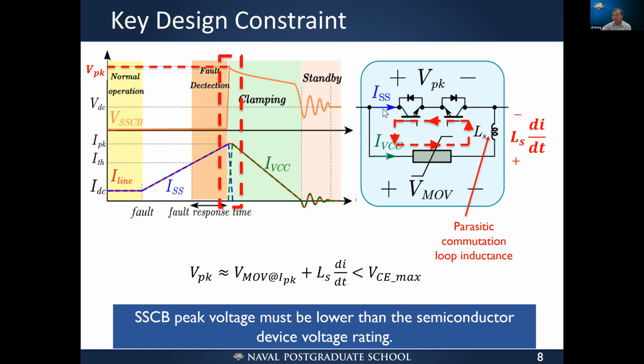And since we are commutating the current from the IGBT to the MOV, you will see a high di/dt. And once you push a high di/dt through an inductor, you will see a voltage. So these two add together to equal the peak voltage. And this voltage must be below the semiconductor device's maximum voltage rating. Otherwise, the device will be damaged almost instantaneously. So this is a key design constraint.